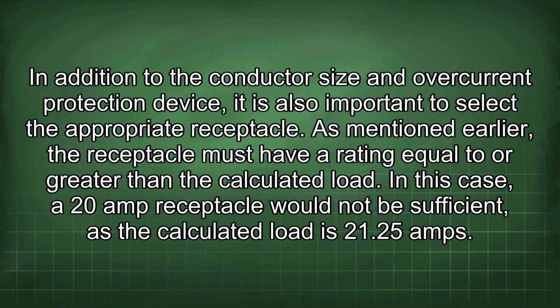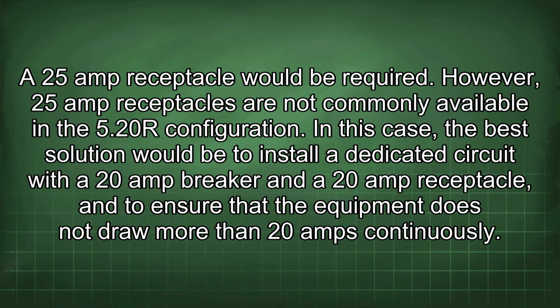As mentioned earlier, the receptacle must have a rating equal to or greater than the calculated load. In this case, a 20 amp receptacle would not be sufficient, as the calculated load is 21.25 amps. A 25 amp receptacle would be required. However, 25 amp receptacles are not commonly available in the 5-20R configuration.